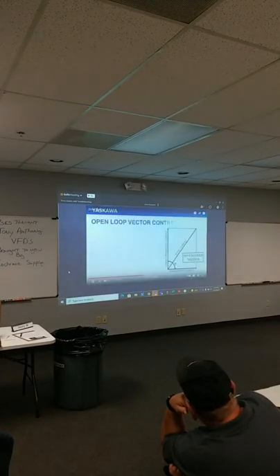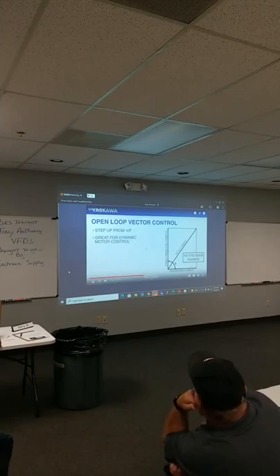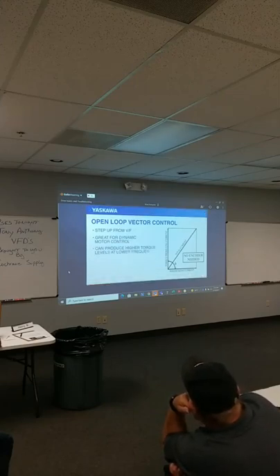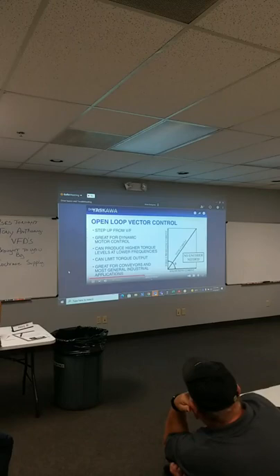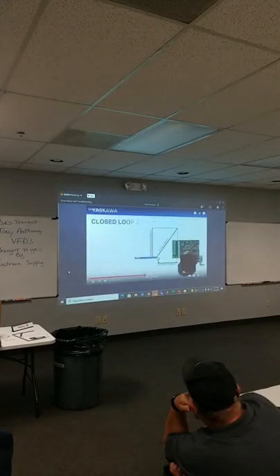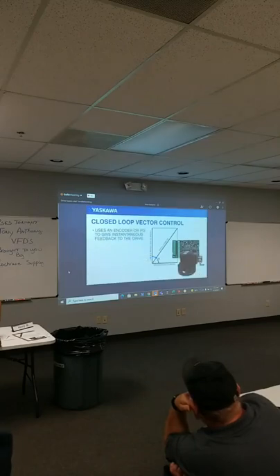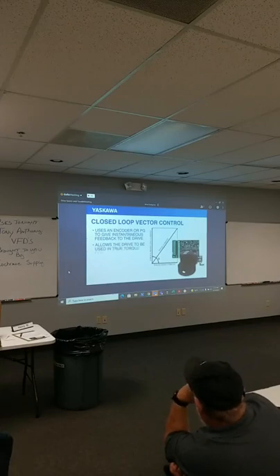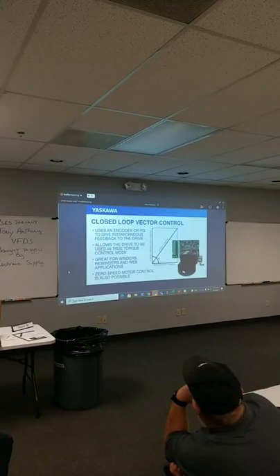Open loop vector control is a step up from VF and is great for dynamic motor control and can produce higher torque levels at lower frequencies. This method can also limit torque output. It's great for conveyors and most other general industrial applications. Closed loop vector control uses an encoder or PG to give instantaneous feedback to the drive. This allows the drive to be used in true torque control mode. This is great for winders, rewinders, and web applications. Zero speed motor control is also possible.